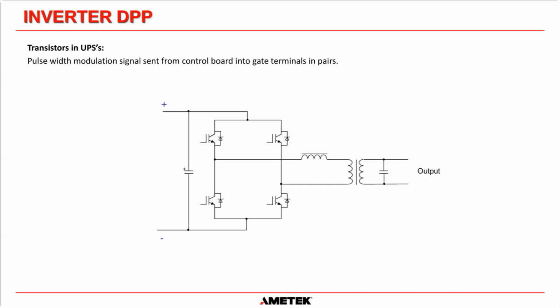When we make UPSs, we know basically that the output of that UPS is going to be tied to an AC distribution panel. Okay, so let's take a 10 kVA UPS or inverter, for example. Now that's going to give you around about 83 amps as an output. So that's going to go to your AC distribution panel, and you are going to have maybe 10 circuits connected to that. So those 10 circuits are probably going to be protected by a 10 amp breaker, something similar to that.